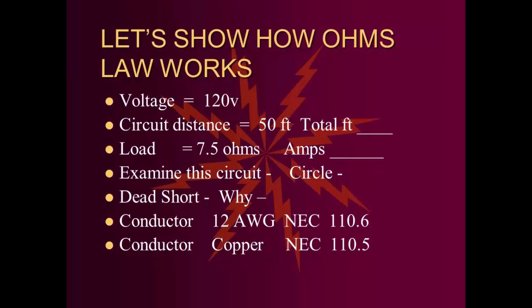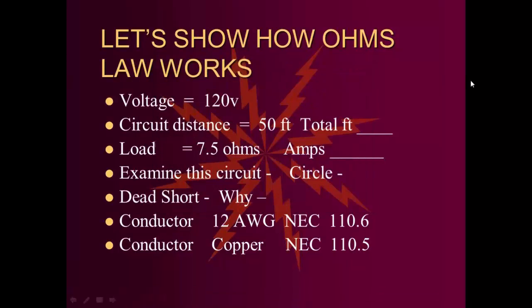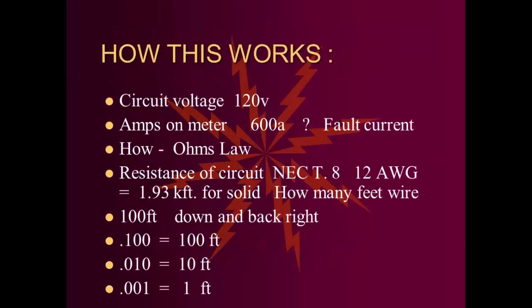correct. Now, as we examine this circuit, we find it dead short, and we've got to find out, well, what's happening here? How do we get 600 amps? Well, the conductor is a 12-gauge wire because it's a 20-amp breaker, and we know the AWG stands for American Wire Gauge because in the NFPA 70, National Electrical Code, in 110.6, it tells us that the gauge is American Wire Gauge. The conductor is going to be copper unless otherwise specified because in 110.5 of that same standard, it tells us it's copper unless otherwise specified. If the circuit is 120 volts, the amps on the meter is 600 amps, that is going to be the fault current.